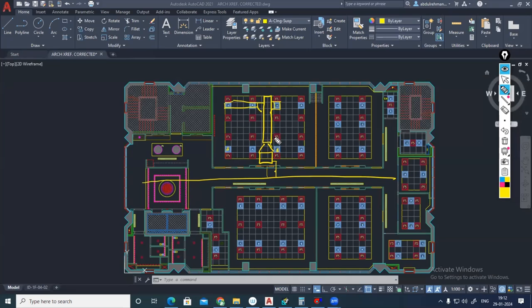After the machine mouth, 1 foot 6 inches, that is 450 mm, only then you have to take the connection. Even if that 450 mm is within the taper, from the taper joint we are not going to take any connection to the diffuser. So after the taper, you can take it. But even then, how can you connect this to the diffuser? You have to take a duct like this. From the duct, you can connect a flexible duct. Or from here, you can make an elbow, and with the help of the elbow you can make a rigid connection there.